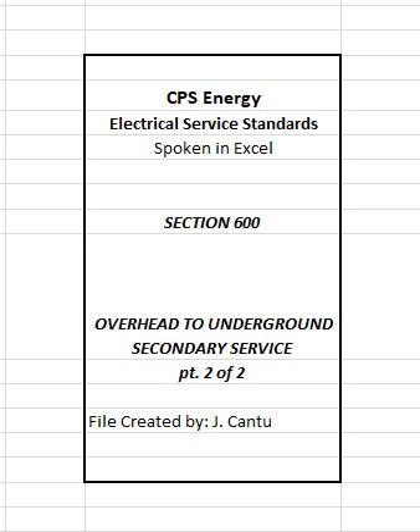604.11 Clearance from other buried utilities. Clearance of service conduits from other buried utilities shall be 12 inches minimum for commercial service installations, and for residential service installations random lay will be permissible. Depth of trench shall be coordinated with CPS Energy's customer service representative to assure minimum clearances are maintained.